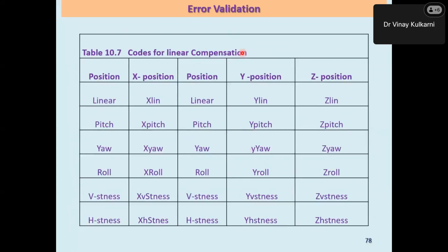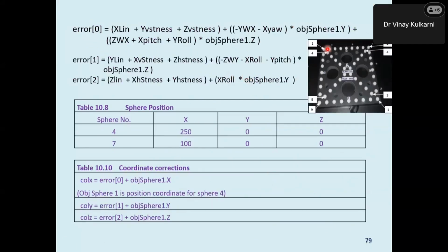So these are the codes that we have developed for linear compensation. And at the same time, dear friends, this is the most important feature in our research that we are trying to make. Obviously, there are residues and more research work is required to make these error statements. So these are the 3 error statements of that particular CMM, so that if there is some error in that pitch and sphere number, we can put this into this, and we can actually compute the compensation value of that particular CMM measurement, which is the most important thing. Let's say, for example, the CMM measurement shows 45 mm diameter, and if you know its compensation value, then obviously we can understand how much extra amount it is committing because of CMM error in computing. That is what we call uncertainty. But just saying that it is uncertain, we are not adding to that. We are adding that uncertainty measurement as a compensation for this particular method, dear friends.